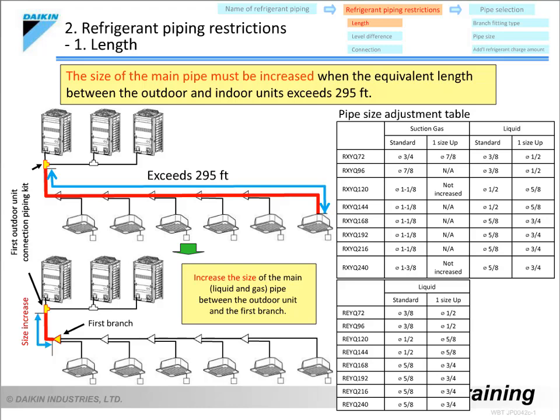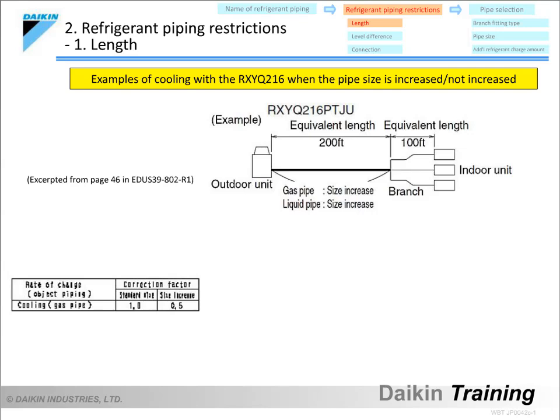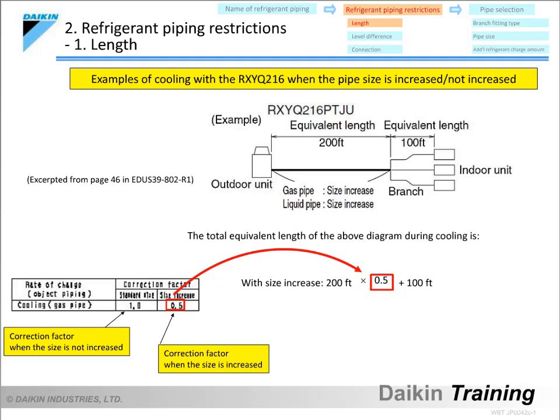Let's look at the cooling operation of an RXYQ216 model as an example. The equivalent length of the main pipe is 200 feet, and the equivalent length of the piping after the first branch is 100 feet. The formula for total equivalent length is: equivalent length of the main pipe multiplied by the capacity correction factor, plus the equivalent length of the piping after the first branch. The capacity correction factor is 0.5 when the main pipe size is increased, and 1.0 when it is not. Accordingly, the total equivalent length is 200 feet with size increase, and 300 feet without.